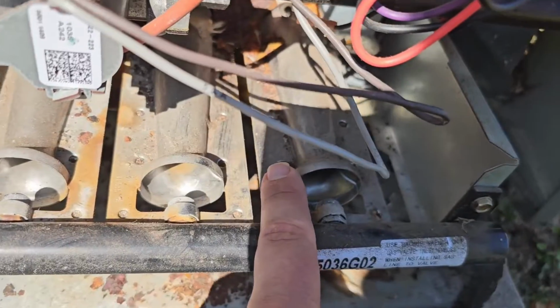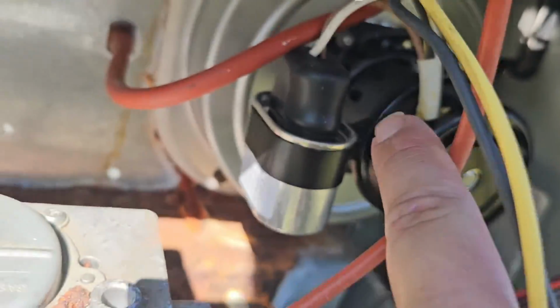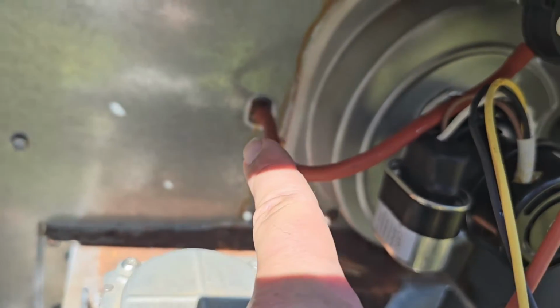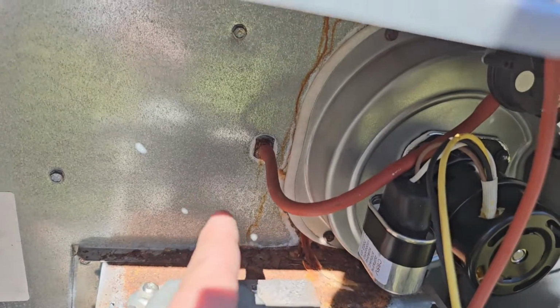Usually always replace the burners, the heat exchanger, and the flue box and the inducer motor together. Burners, inducer motor, and then usually the flue box cover is what the inducer motor is mounted on.